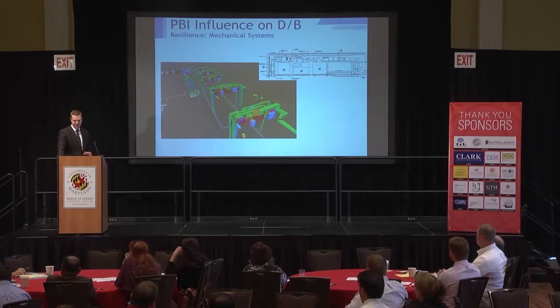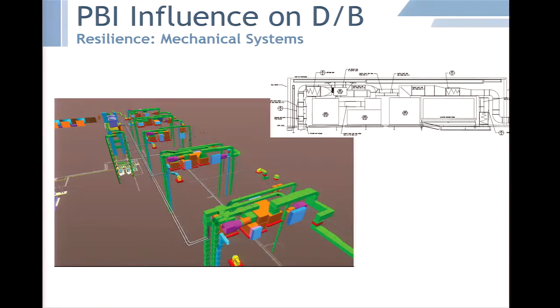Within each of those penthouses, we had the concept of redundancy. In the upper right, these 3 boxes in the diagram are each an air handling unit. Those air handling units have variable frequency drives, and they're headered together at the top. On any given day, under normal function, they operate independently and that header is separated. But if there's a need for routine or unexpected maintenance on any one of those air handling units, the system can be headered together, and the two remaining units with variable frequency drives ramped up are able to serve the needs of the remaining building on, say, 98% of days, given the climate of Long Beach.